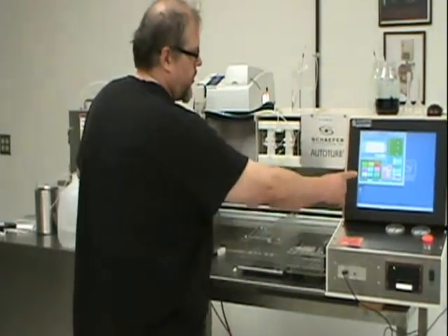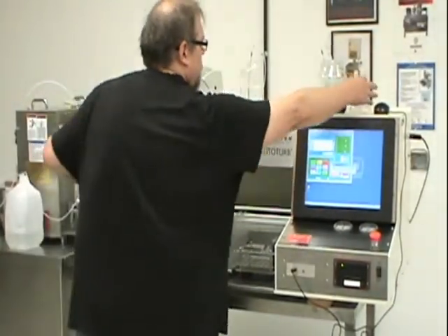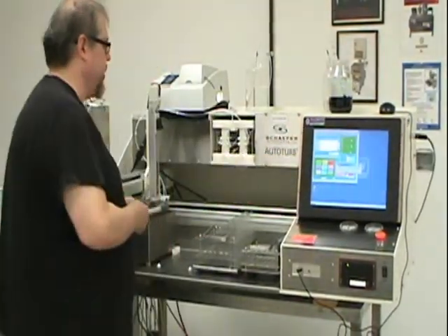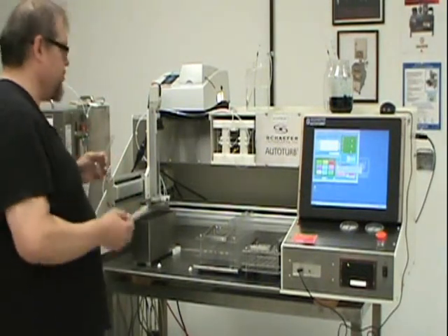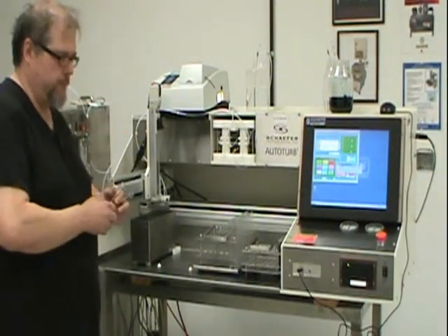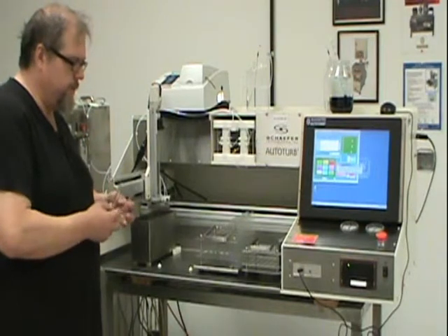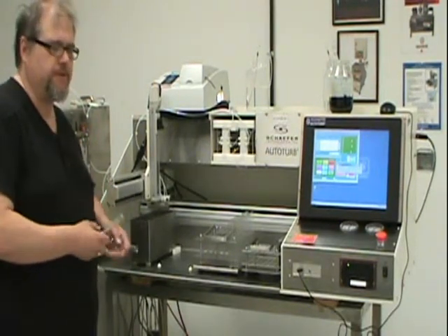That's done, we'll calibrate the pump. We do 5 shots or 5 flush cycles of the syringe pump into 50 milliliter volumetrics. We're looking for 50 mils in 5 shots, which is 10 per shot.